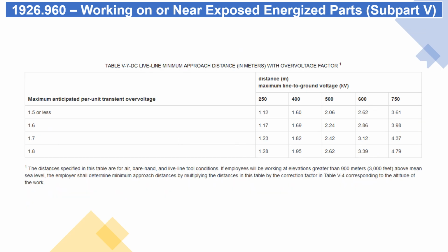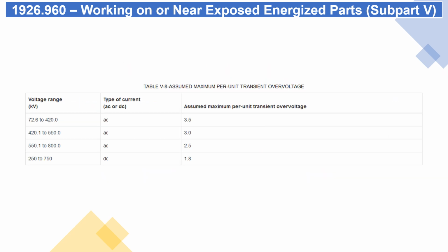Table V7, DC live-line minimum approach distance, in meters, with overvoltage factor. The distances specified in this table are for air, bare hand, and live-line tool conditions. If employees will be working at elevations greater than 900 meters, 3,000 feet, above mean sea level, the employer shall determine minimum approach distances by multiplying the distances in this table by the correction factor in Table V4 corresponding to the altitude of the work. Table V8, assumed maximum per-unit transient overvoltage.